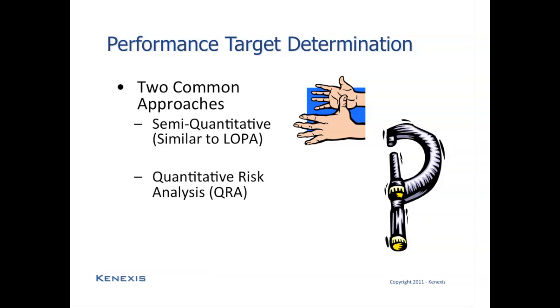The other approach is to use a fully quantitative risk analysis to verify that your quantitative tolerable risk goals have been achieved for each zone. And while the quantitative risk analysis technique is going to provide much more accurate results, it is also extremely time-consuming and very expensive. So as a result, most organizations tend to want to use a semi-quantitative approach that has been calibrated using quantitative risk analysis techniques.